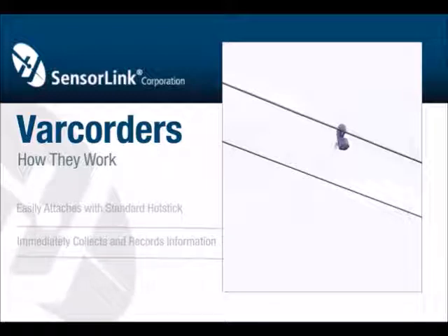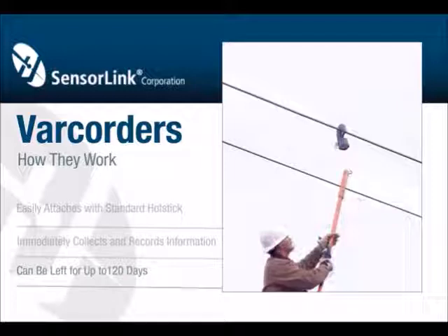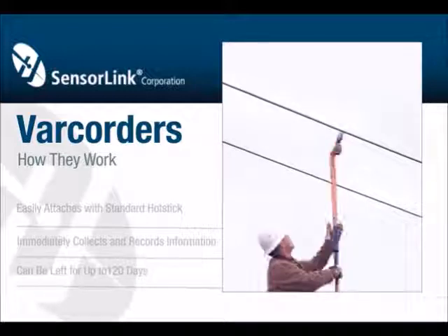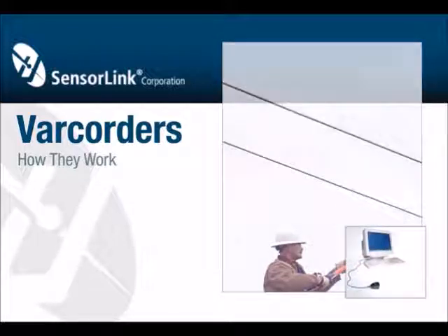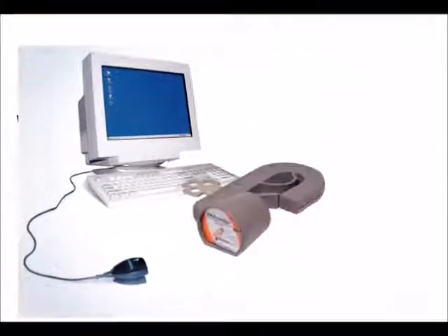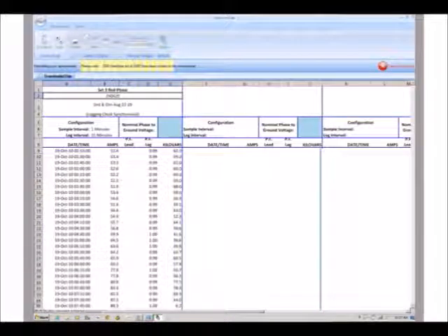The Varcorder can be left on the line for up to 120 days, at which time it's easily retrieved, complete with captured data. The Varcorder is now ready to download its data into your PC through Sensorlink's Softlink software. Simply position the Varcorder in front of the infrared serial port and double-click the Softlink icon on your PC. Select the download icon, and Softlink will download the data from your Varcorder.